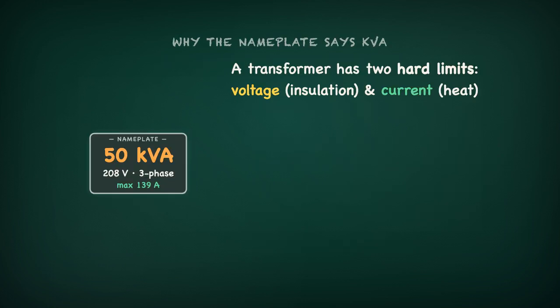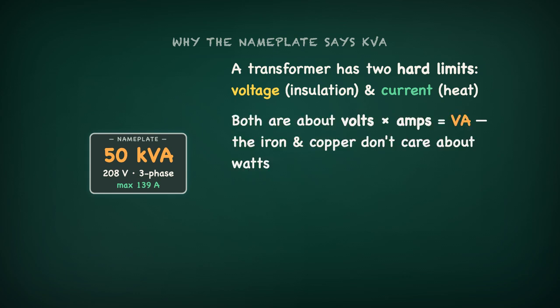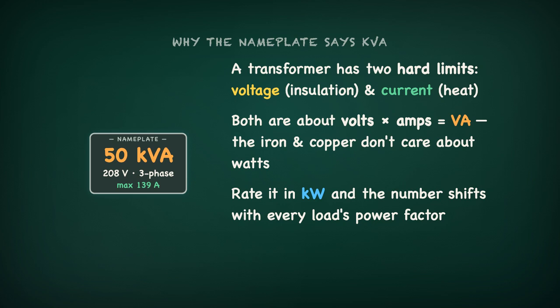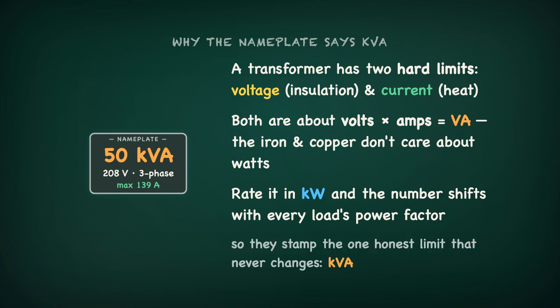So why does the nameplate say kilovolt amps? Because a transformer has two hard limits. Voltage, set by its insulation, and current, set by heat. Both of those are about volts and amps. Volt amps, not watts. The iron and copper don't care how much real work the load is doing. Rate it in kilowatts, and the number would change with every customer's power factor. The manufacturer can't possibly know that.